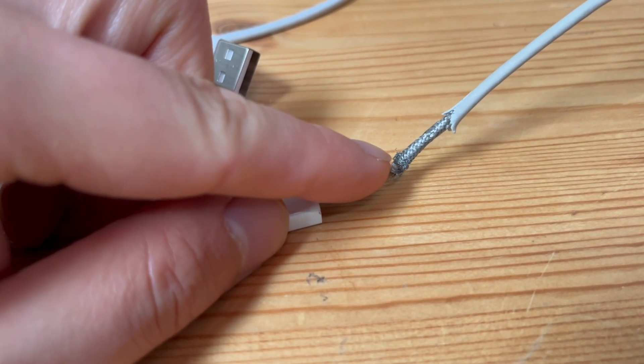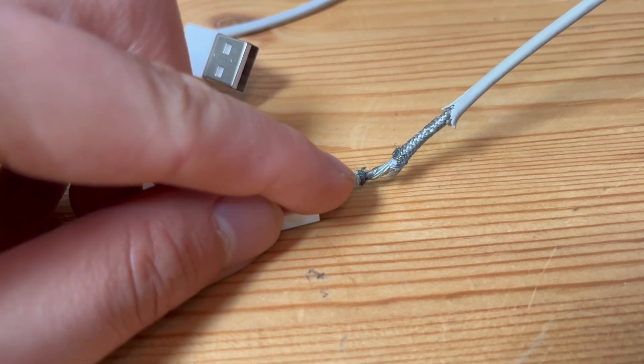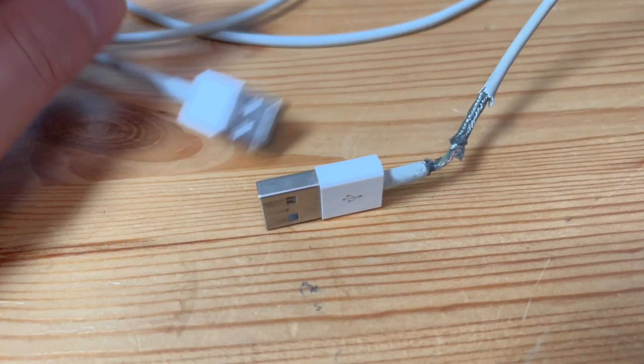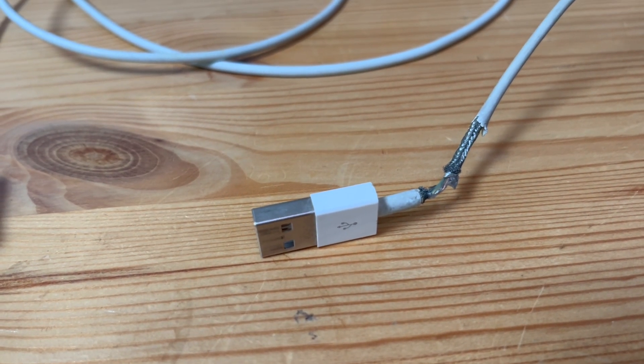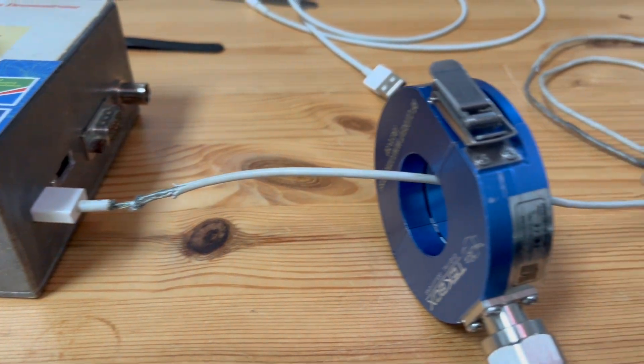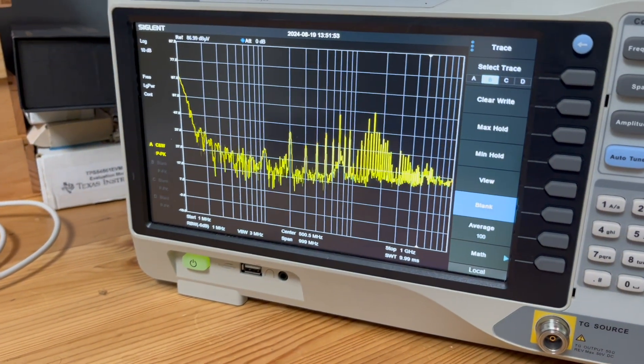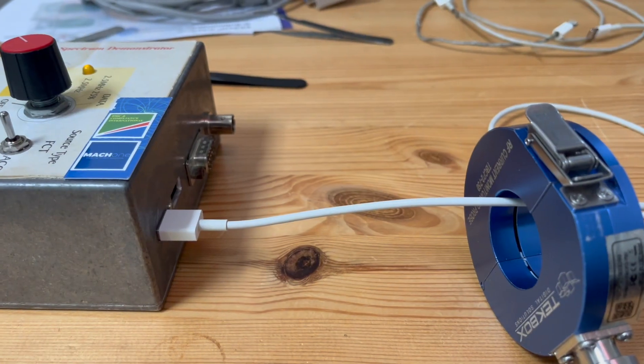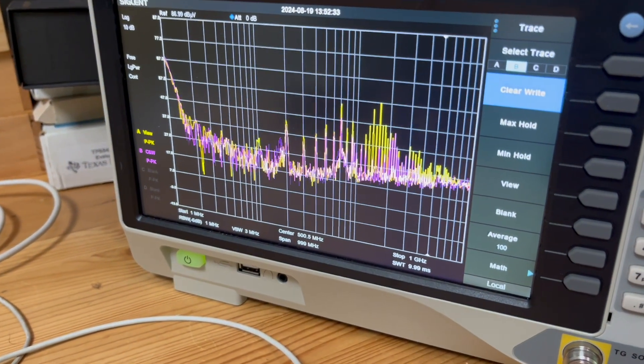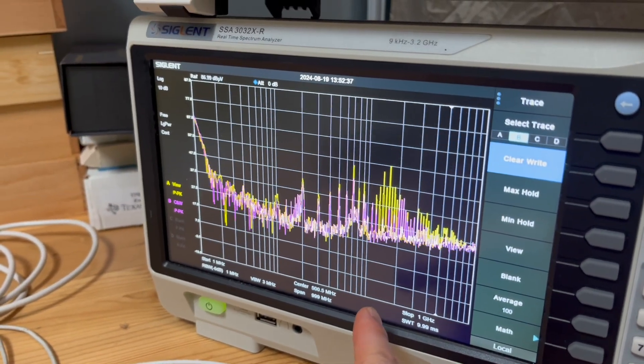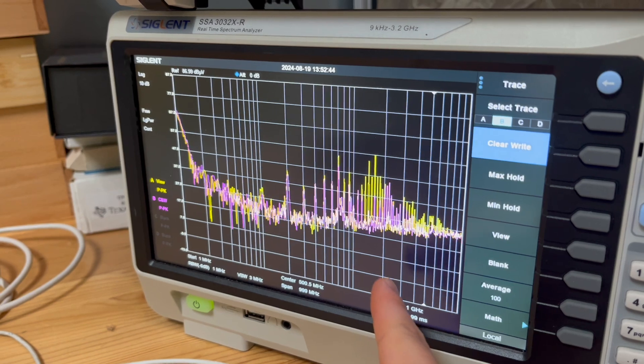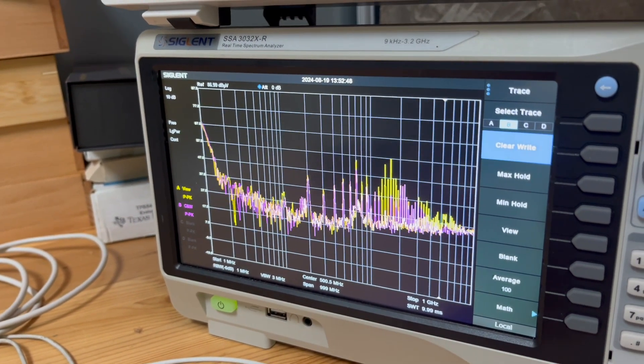To compare the two different constructions: this one you can treat as the outside shield is not terminated, but only connected with a drain wire. We're going to have a quick look at the difference between a fully terminated shielded cable and this kind of poorly connected cable. That is the destroyed shielded cable connection, and this is the frequency performance. Now we switched to the properly terminated shielded cable and you can see the difference. Particularly from high frequency — 100 MHz up to 1 GHz — you can see a reduction between 100 and 200 MHz, more than 10 to 20 dB reduction easily achieved by terminating the shield properly.